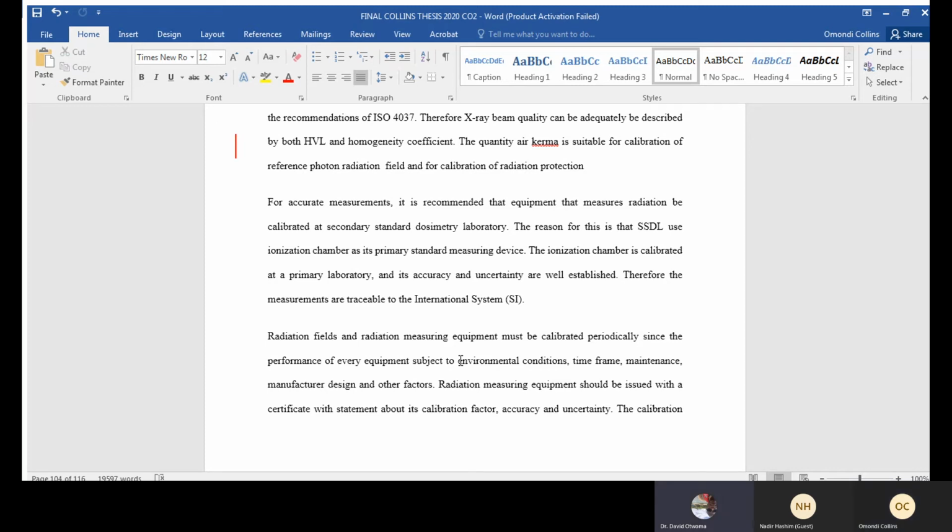And that is how now you bring out the fact that it's important to do more research, because the ionization chambers are sensitive, they are reliable, and show good energy response to X-ray and gamma radiation. They should be maintained and kept carefully in the dry cabinet if they aren't in use. Because if you do poor maintenance, you'll have scenarios where you think it is a high background reading of the survey meter, you think it is due to leakage radiation, but that is for other research to do, not this one. You have to point out where the holes are in what you've done, and invite other people to continue where you've arrived.